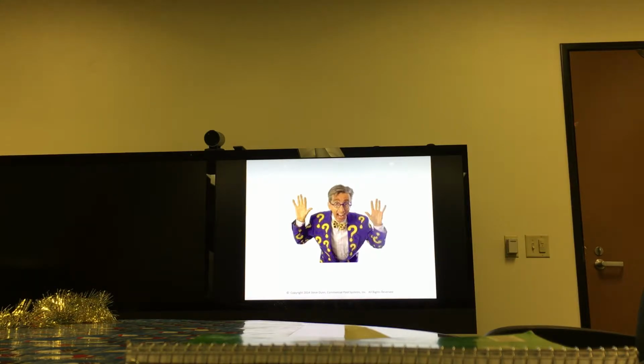Now, we're putting this box together ourselves. We could do that as a pool. I mean, this is nothing new. We're just doing it in a box in our shop, as opposed to doing it out in the field, which a pool guy can do. The difference might be that there was a third item in there. It's a transformer. We're taking the voltage going out to the flow switch and dropping it down from 115 volts to low voltage, in the 12 to 24 volt range.